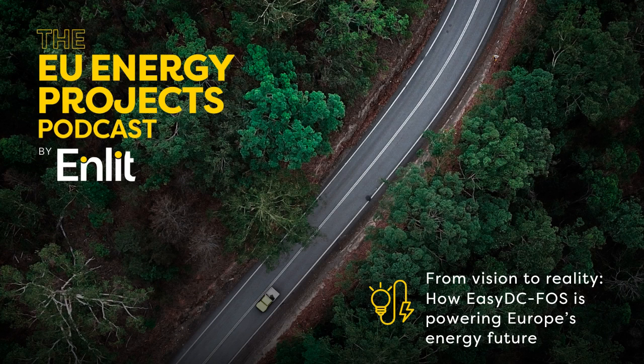The second one is the cost of installation. Right now, if you want very high loads to compensate and do the exchange between AC and DC in the power grid, you need very big valve stations. The same thing happens here: if we can do it with lower voltage levels, sticking to 525 kV, the valve station for AC to DC conversion will be smaller, less costly, and easier to build.